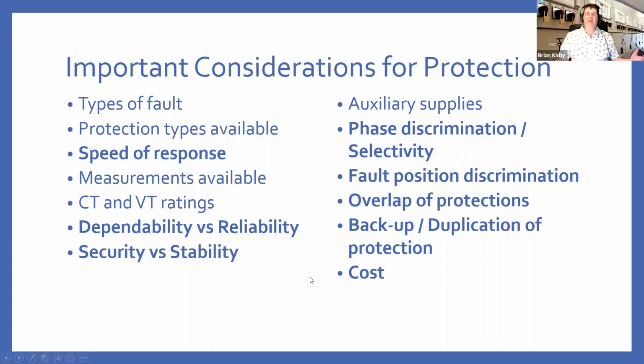Typically they're set by either the distribution company or the transmission company, who will have their standard availability for those things. The next two are the key things you need to look at in terms of long-term operating. You need to be dependable but reliable. I will go into more detail on what those are in a later slide. Similarly with security and stability, I will address a bit more about those later on. Auxiliary supplies, again, most substations now will have some sort of battery backup system to run your secondary equipment, but usually that's something that the customer specifies.